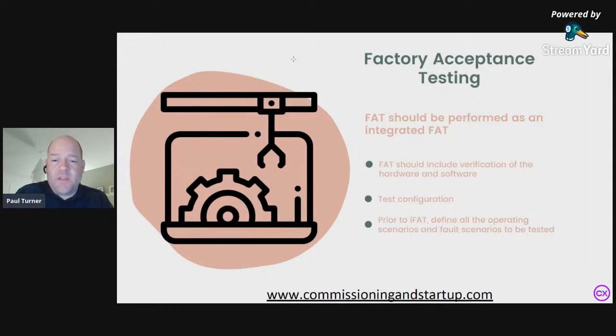I've also seen this done the other way, where the software is not ready, it's only half written, you only partially go through verification of the software, and there's always pressure to ship the hardware to site. Someone decides, okay, good enough for factory acceptance test. After 2 or 3 days, we're shipping the hardware to site. That causes nothing but problems.